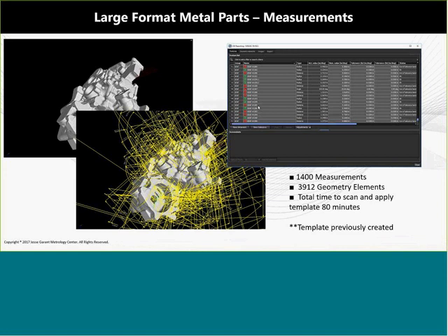What it allows you to do is create a full CMM template inside the software with tolerances. The beauty of this is that you're able to actually see how the measurements are made and where they're taken. You can see when a line is fitted between two bosses and then dimensions. You can actually see that. It gives your engineers tremendous amounts of power.